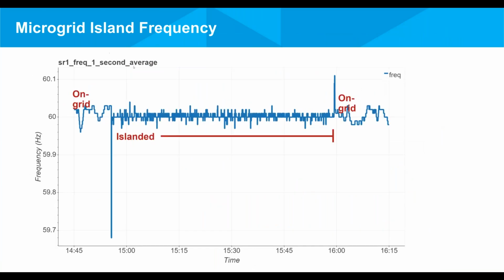Here's the chart depicting the frequency during that second islanding event. What you see here is that while the system was on grid, the frequency band was not as tight, but when the smart homes were islanded by the microgrid, the frequency band was much tighter. And after the hour, when the smart neighborhood was reconnected with the grid, the frequency band was wider again.